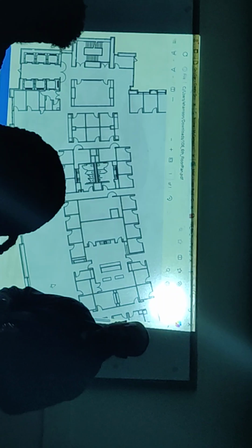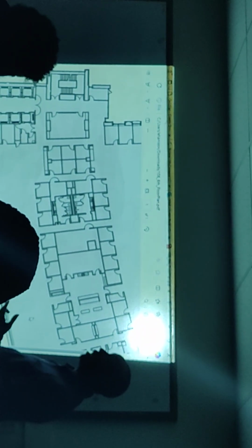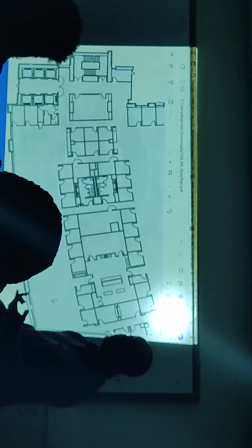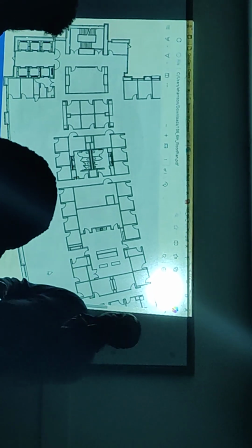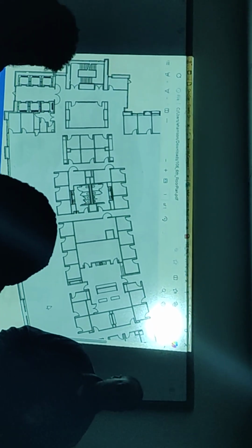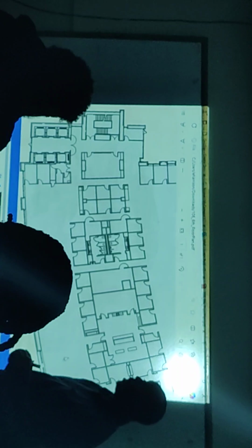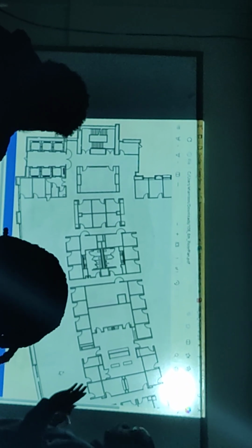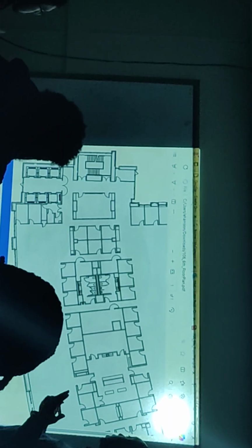When you're thinking about engineering, whether you're doing your house, whatever, you always have to think about where you're putting this stuff so that it makes sense, so that it's efficient cost-wise as well as energy-wise. It's got to make sense that you get good airflow in these areas. Where you put them makes a difference. So for instance, what you'll usually have is 1 VAV per thermostat, all right? Remember this, 1 VAV per thermostat. Now, with that being said, a VAV can supply whatever you want it to supply. If you want to supply this whole area with 1 VAV, then that's on you. It probably won't work that well, but that's on you.